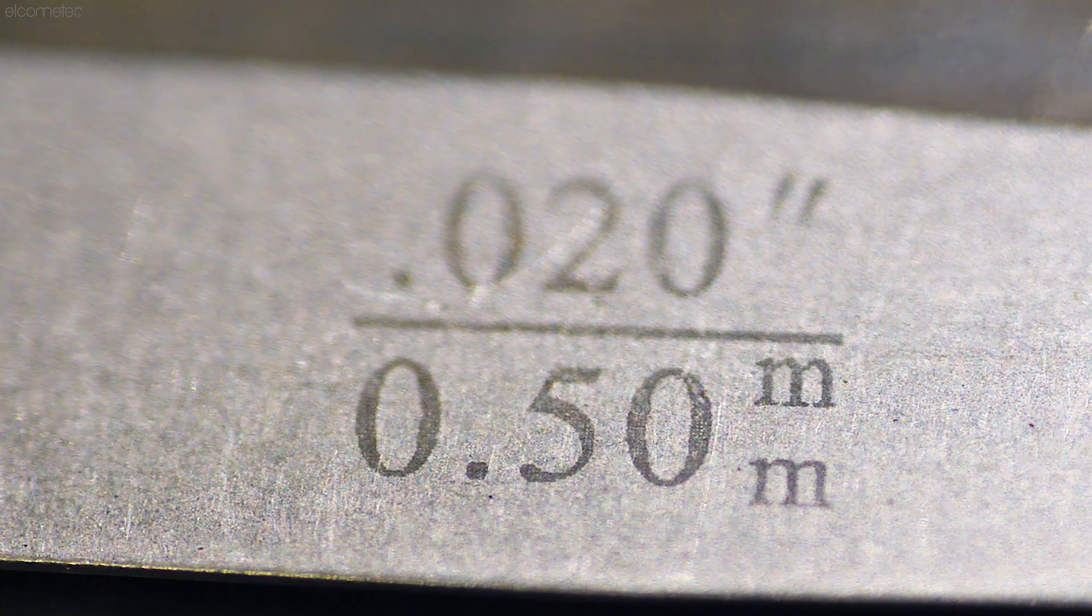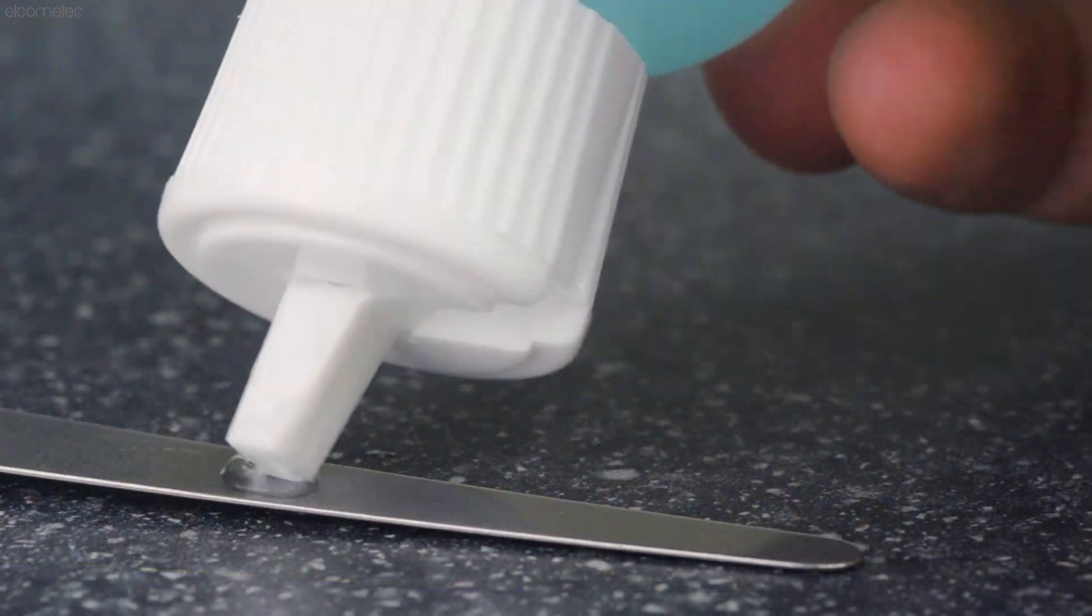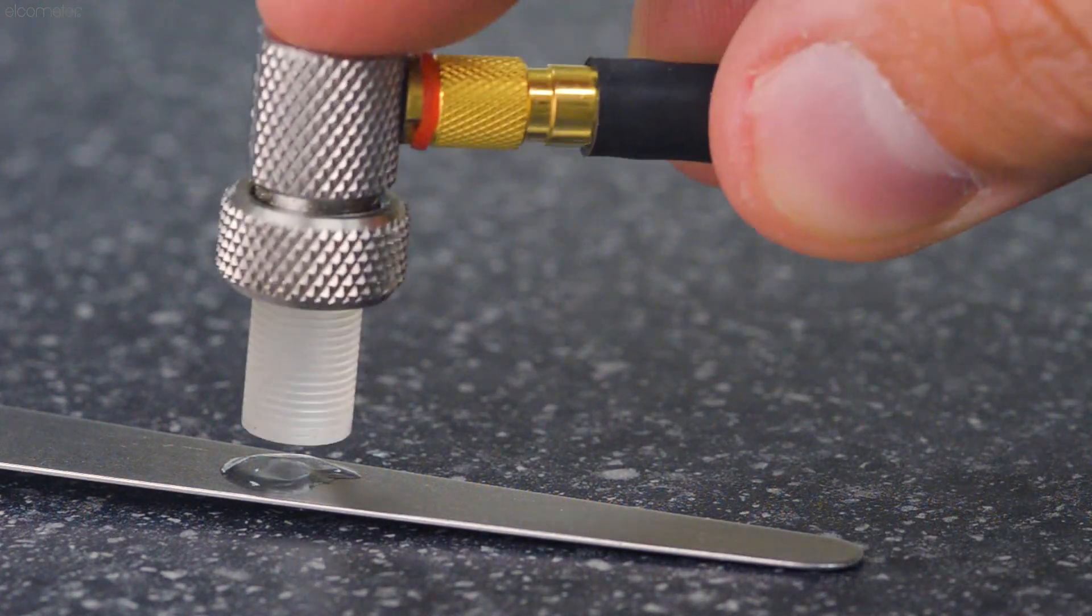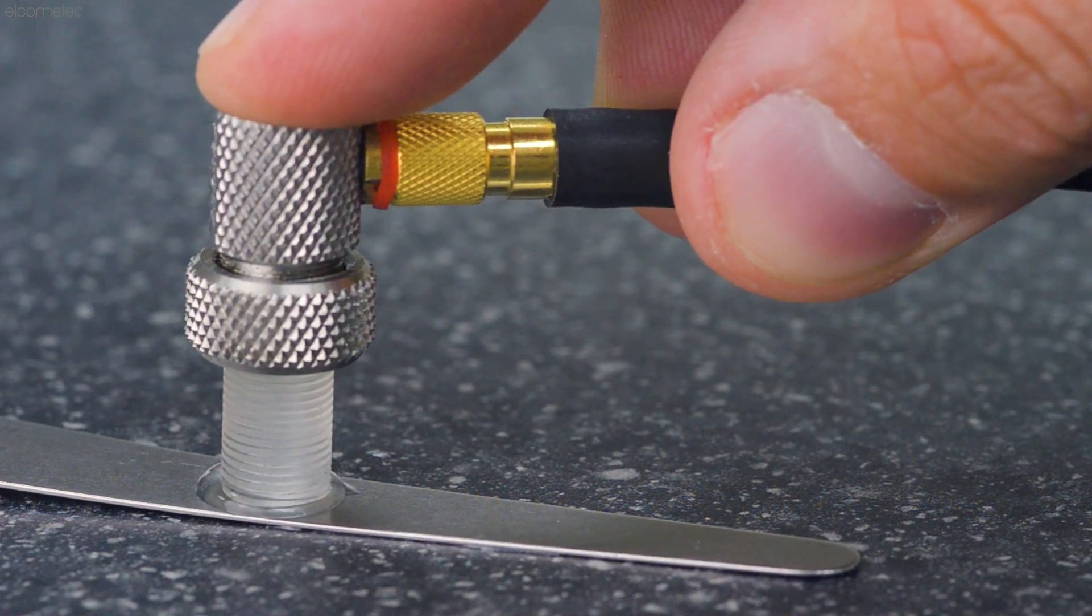Taking a reading on very thin substrates when accuracy is critical couldn't be easier. Using a very small amount of ultrasonic couplant, press the transducer flat against the surface.